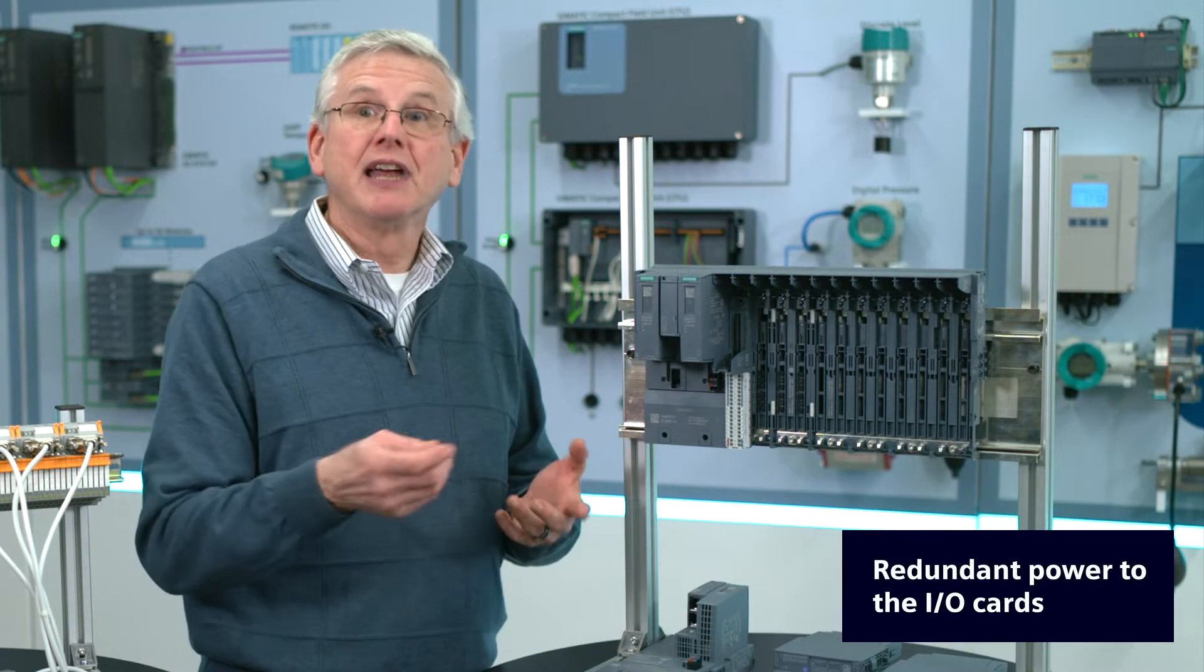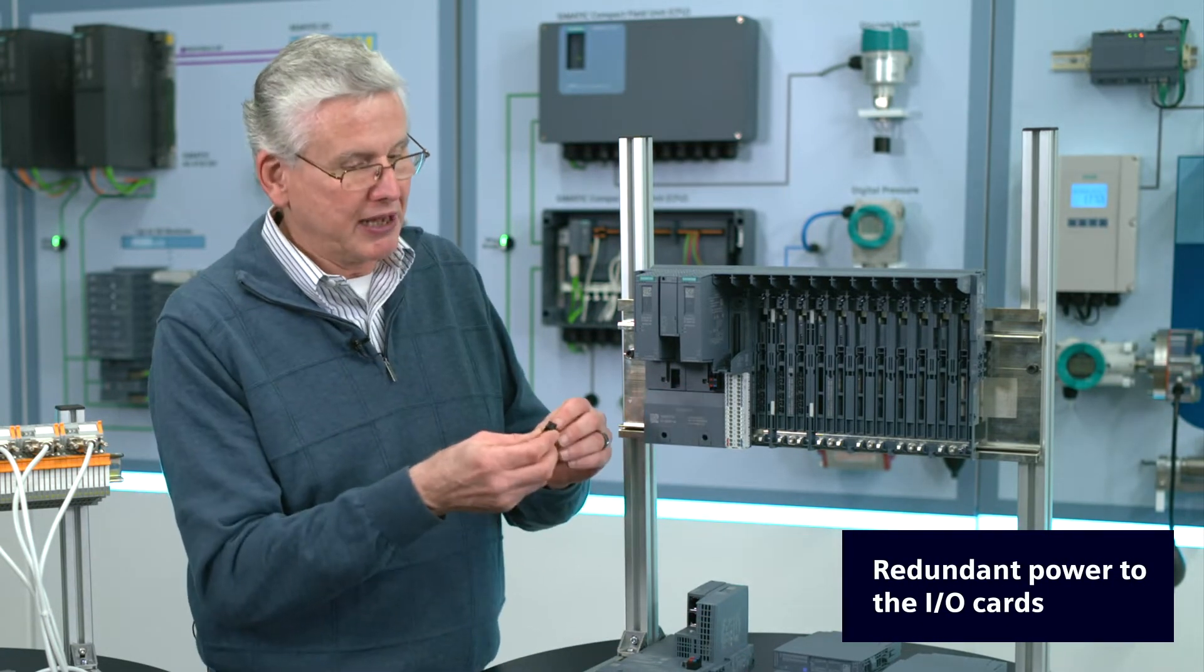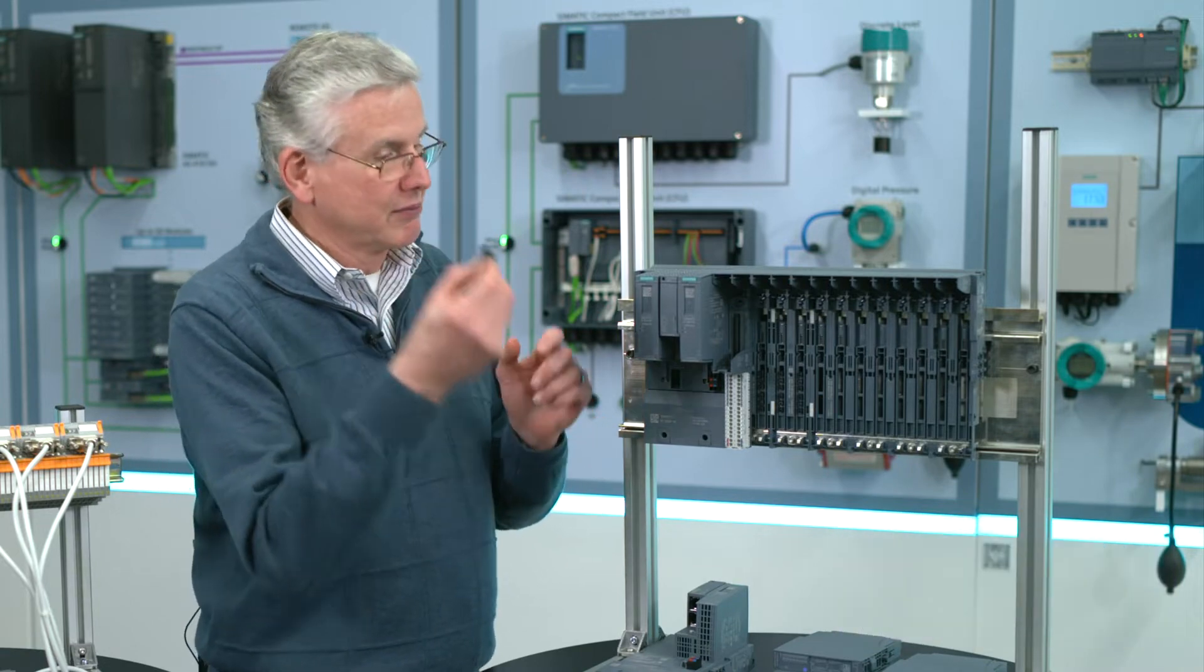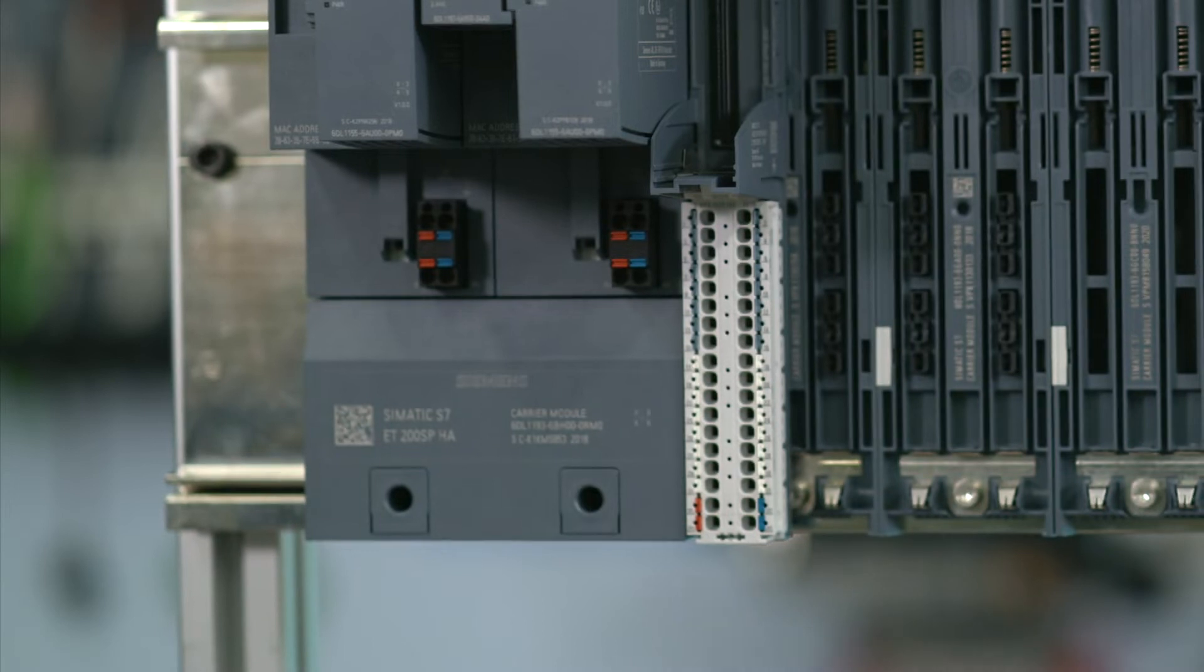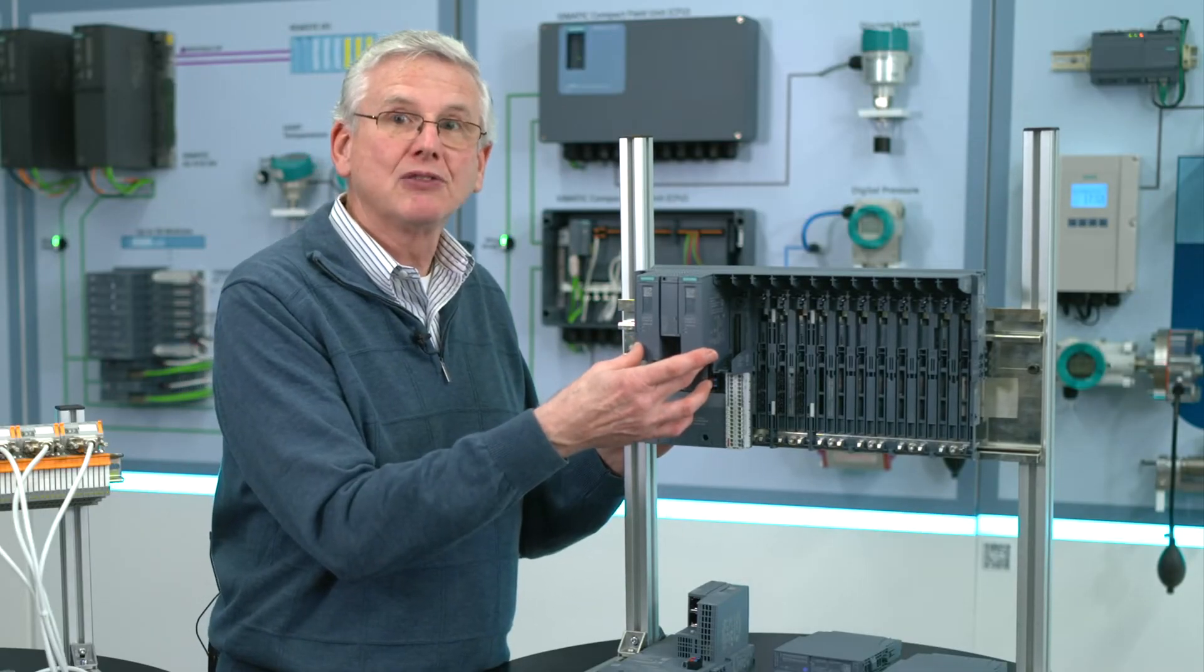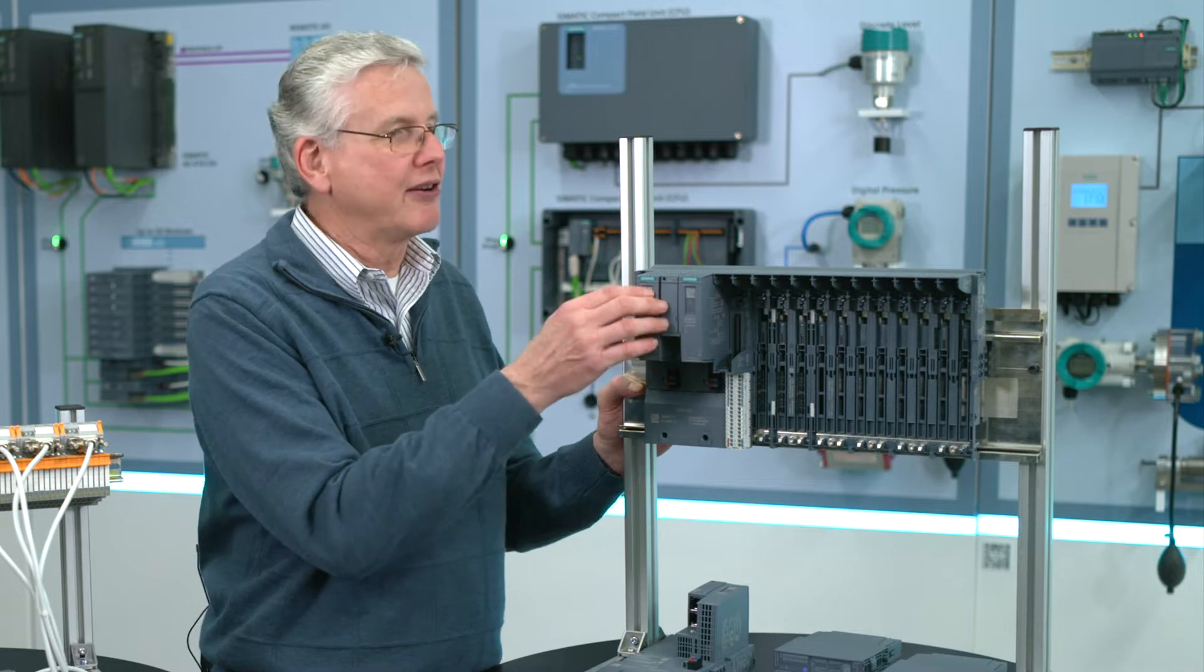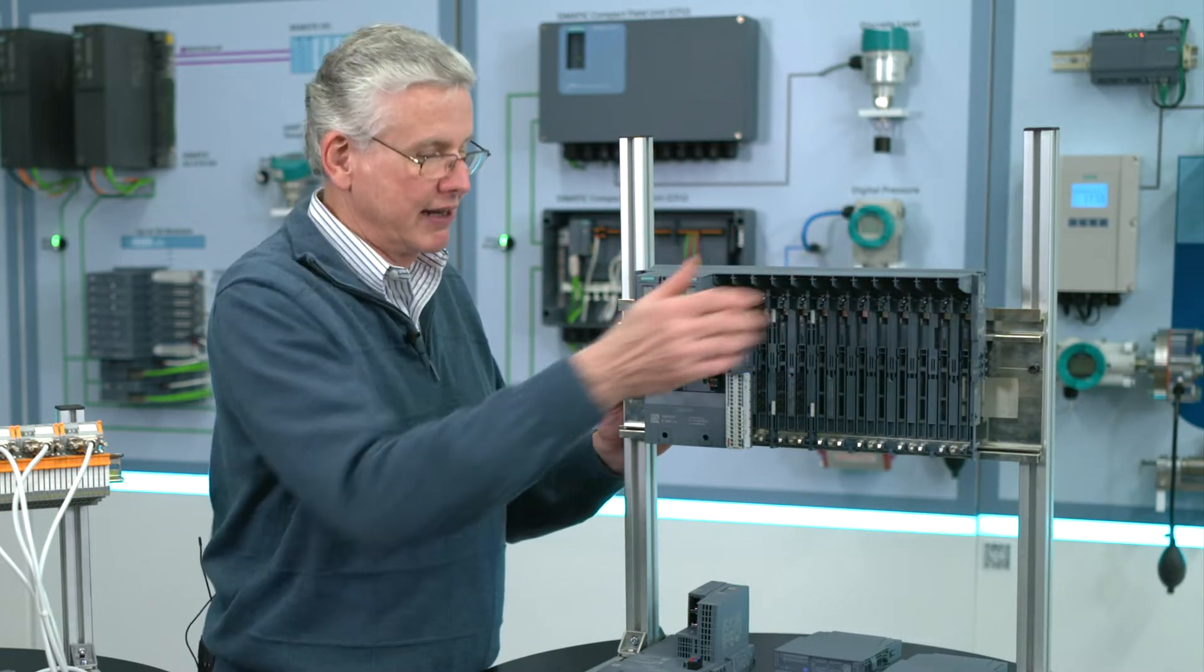And I talked about redundant power. On each of the IMs, there's a place for power. So we just have to plug in that little connector, and that gives me a place to bring in power. So power comes into both interface modules, and then basically it's OR'd together and provides all the power for the module electronics that are in the rail itself.